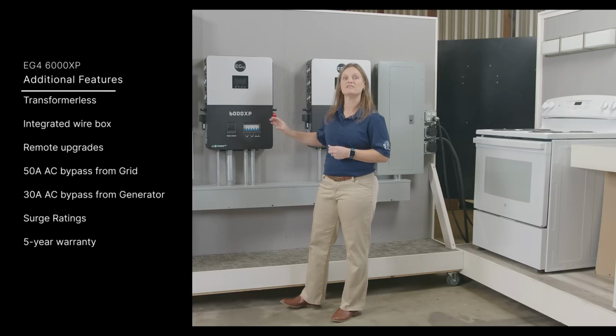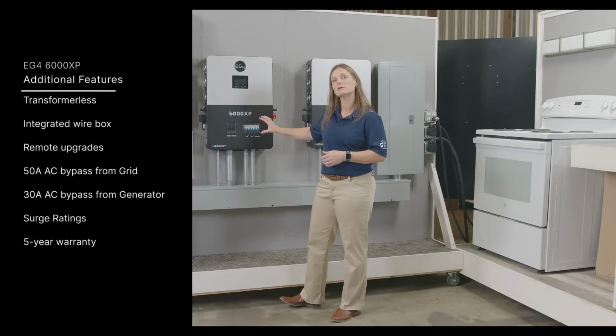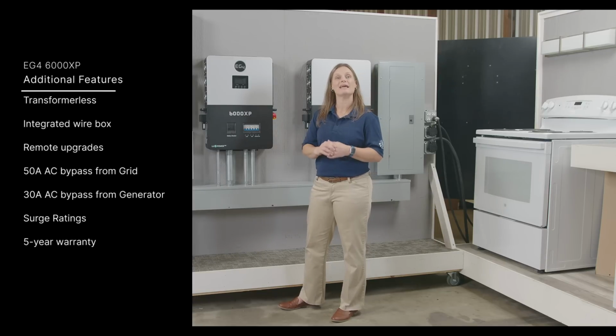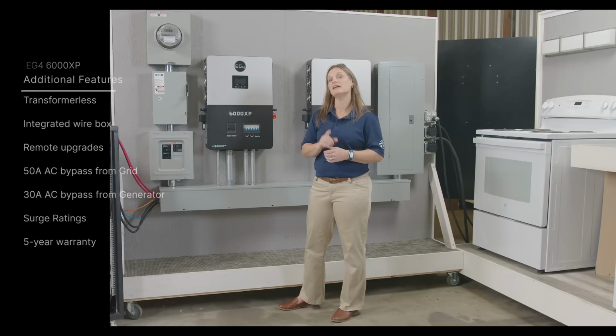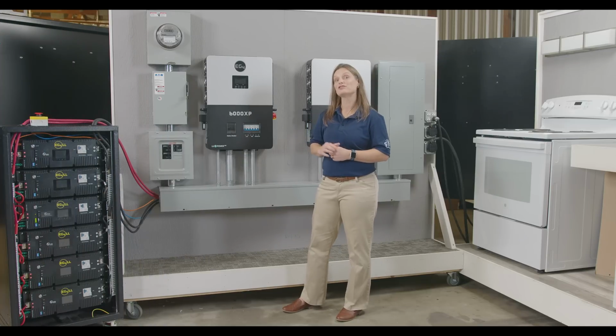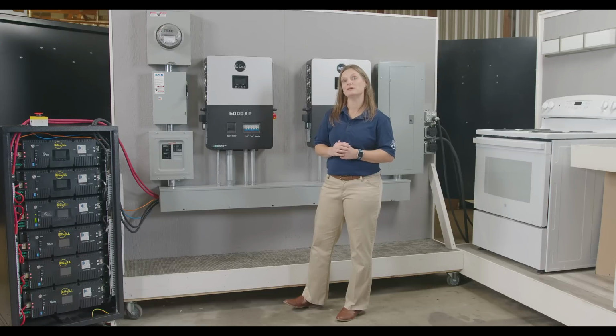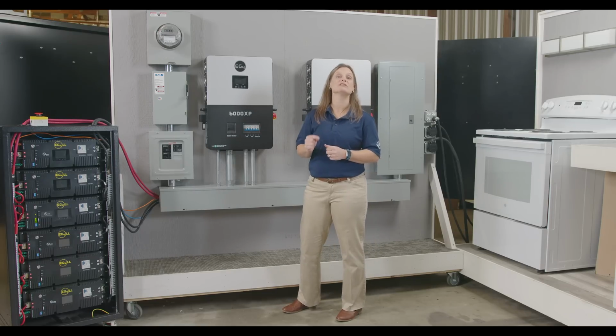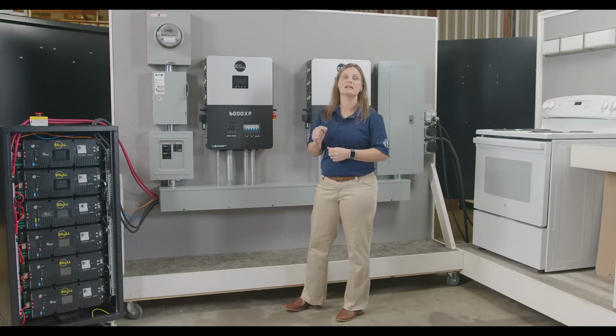Don't forget that this device also allows the convenience of remote fine-tuning and firmware upgrades through the EG4 software. Plus, it comes with a 50 amp AC bypass from the grid and a 30 amp AC bypass from a generator, offering you even more flexibility and control. This inverter's got your back during power spikes too. It can handle 12 kilowatts for roughly 3.5 seconds and 11 kilowatts for around 5 seconds.